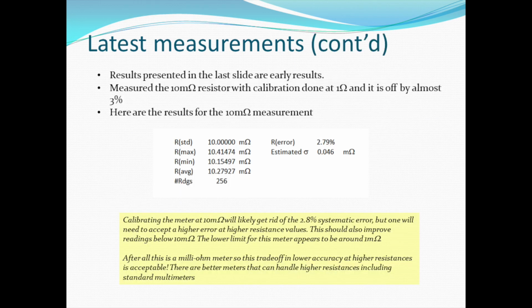So next I took the 10 milliohm resistor and I measured that with the calibration done at 1 ohm. This is to confirm how much slope error there is, or even offsets that may be present in the meter. In this particular case you can see that the standard resistor I assume is exactly 10 milliohms, and the R max is 10.41474 milliohms, and then the R min is roughly 10.155 milliohms. So the average came out to be 10.2793 milliohms or so. Over 256 readings, the R error is about 2.8%, and the estimated sigma for this is around 0.05 milliohms, or roughly 50 micro ohms.